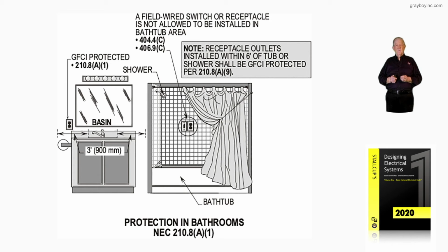Be very careful about putting a hanging fixture over the bathtub, a fan. Many homeowners want this done. And some electricians will do it when they're providing GFCI protection for the circuit. But let me point out that if somebody got killed in that tub due to a faulty GFCI for any reason, the electrician would be held responsible, and so would the contractor.